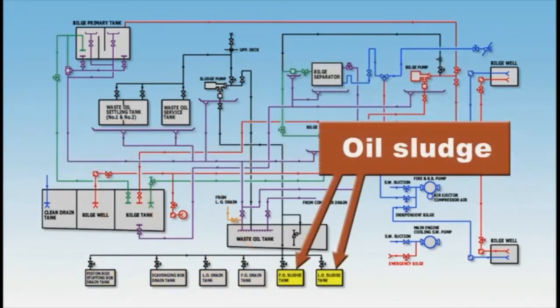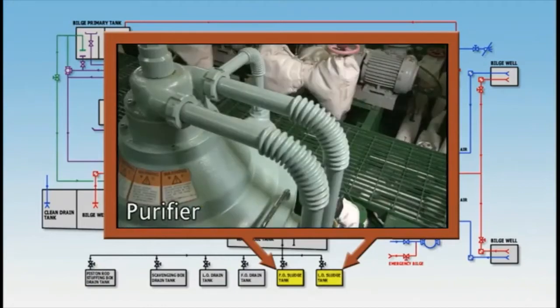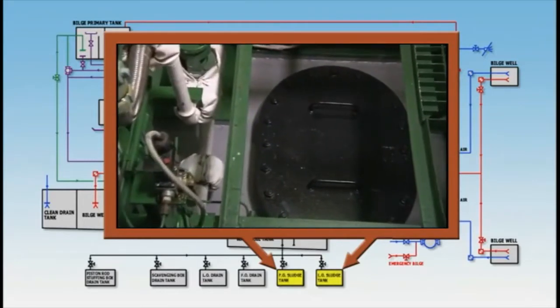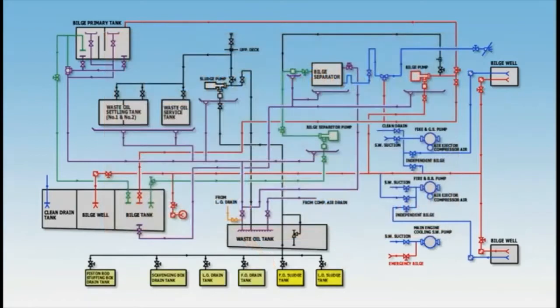Oil sludge is foreign matter other than oil from the fuel oil and lubricating oil purifiers. Heavy fuel oil for marine engines is used only after impurities such as water and carbonic solids have been removed with a purifier. These impurities can account for around 1% of the fuel oil consumed, meaning a ship consuming 100 tonnes of fuel oil every day can generate as much as 1 tonne of foreign matter. Oily drain and sludge are also known as oily bilge, and using a sludge pump, they are transferred from the sludge tank and oily drain tank and collected in the waste oil tank.